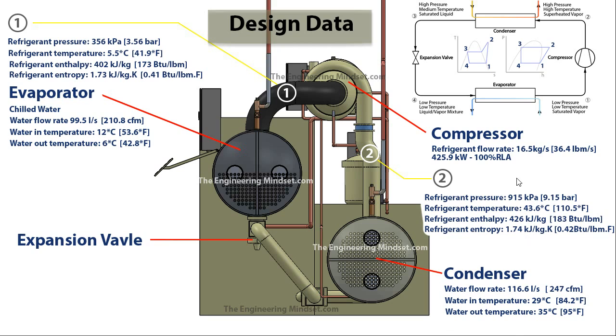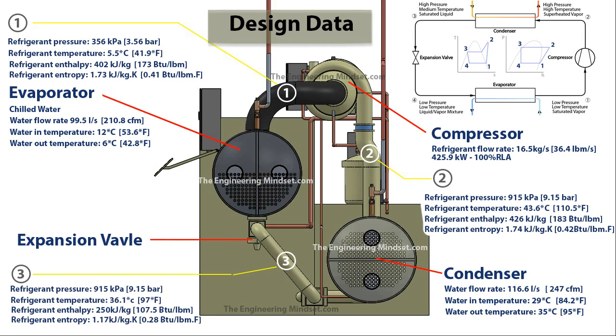Remember, the temperature of the refrigerant entering the condenser has to be higher than the water temperature in the condenser to enable heat transfer to occur and for the condenser to reject that heat. If they were the same temperature, no heat transfer would occur and the chiller would do no cooling.